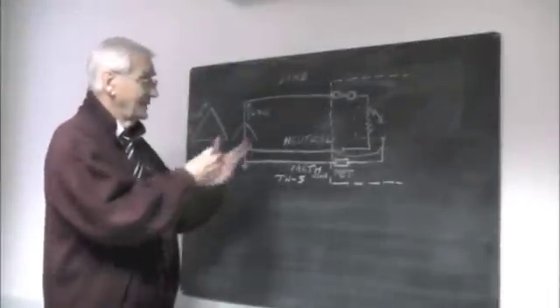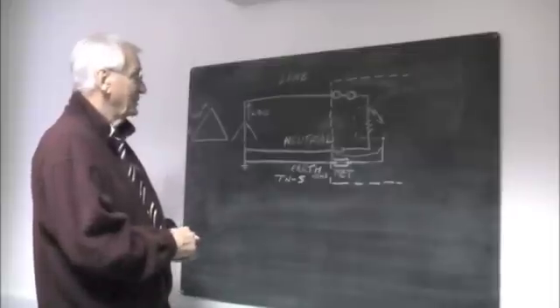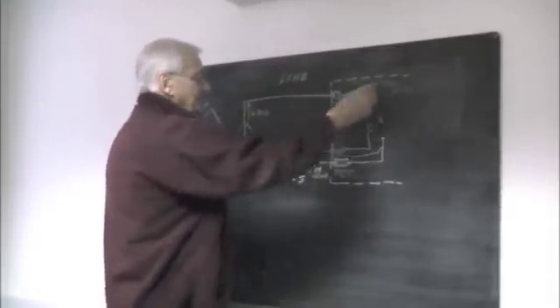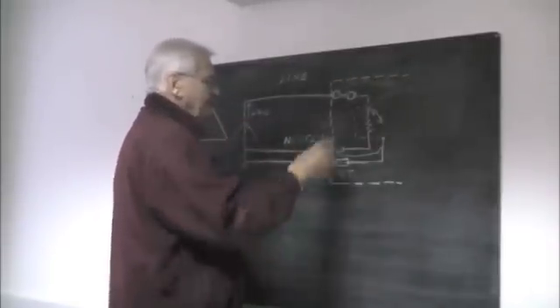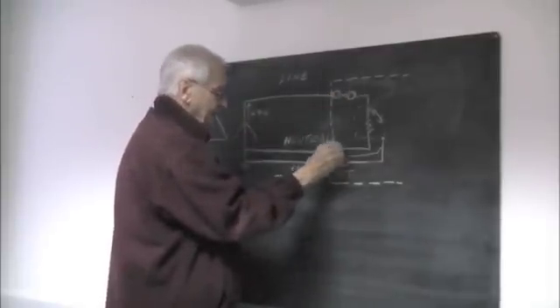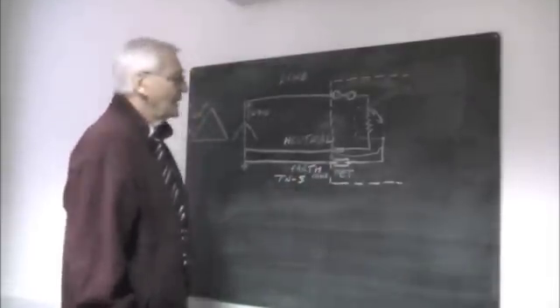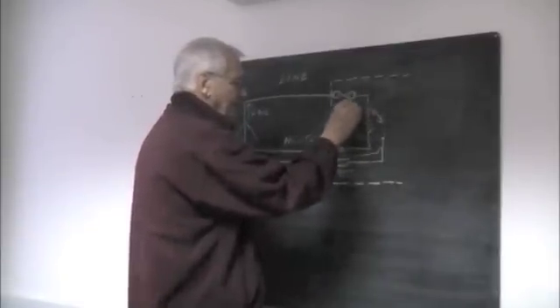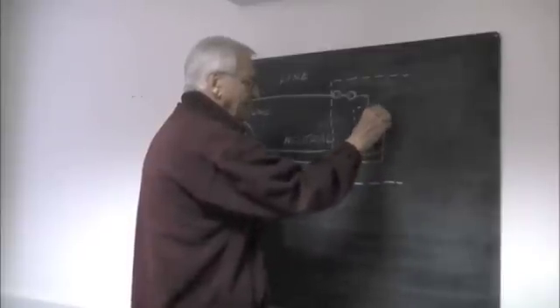I'm going to show you exactly where you measure the ZE and for that matter the ZS as well. It's nice to know exactly what you're measuring when you do these jobs. So you can see I've got the transformer I showed you. This demarks the building line of the installation that we're doing here. This is the intake point, the first protective device into the system which I've shown as a fuse. This is the neutral coming into the system and this is the main earth terminal. I've shown a piece of equipment in the system and an exposed metal conductive part around that piece of equipment like so.